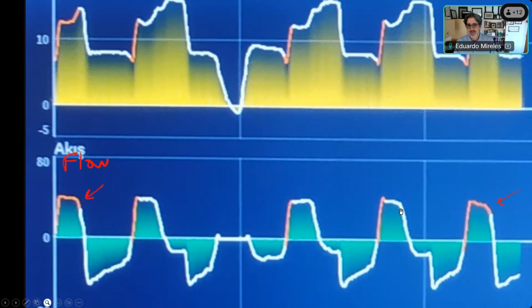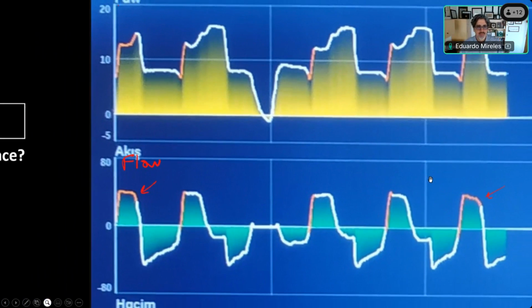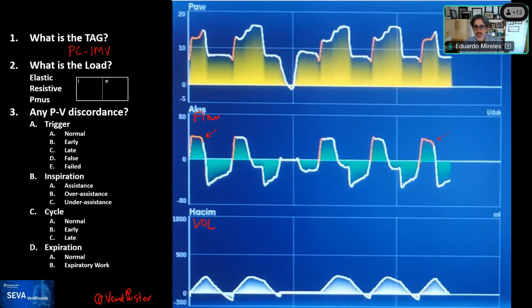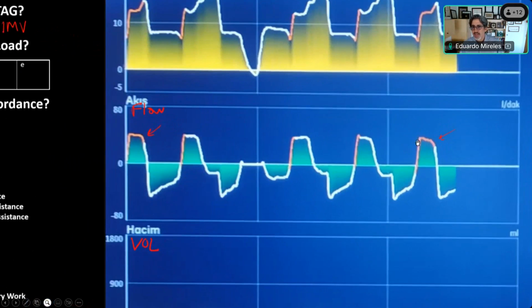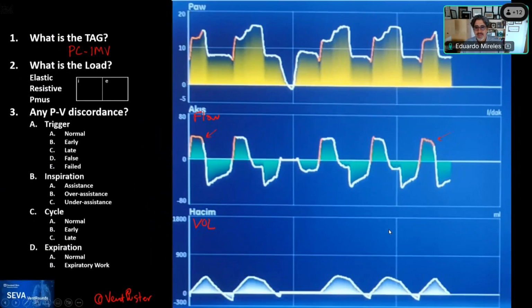So again, I think that this is a back to the manual and trying to understand this. But if this is happening regularly, I think some of the RTs on the line are putting, well, you need to change the sensor calibration and see what's going on. But this is important, and I would applaud Vent Busters, because when you get these images, this is what helps us understand what the ventilator does in real time. And without them, we cannot tell. Sometimes the manuals don't even go in that depth.